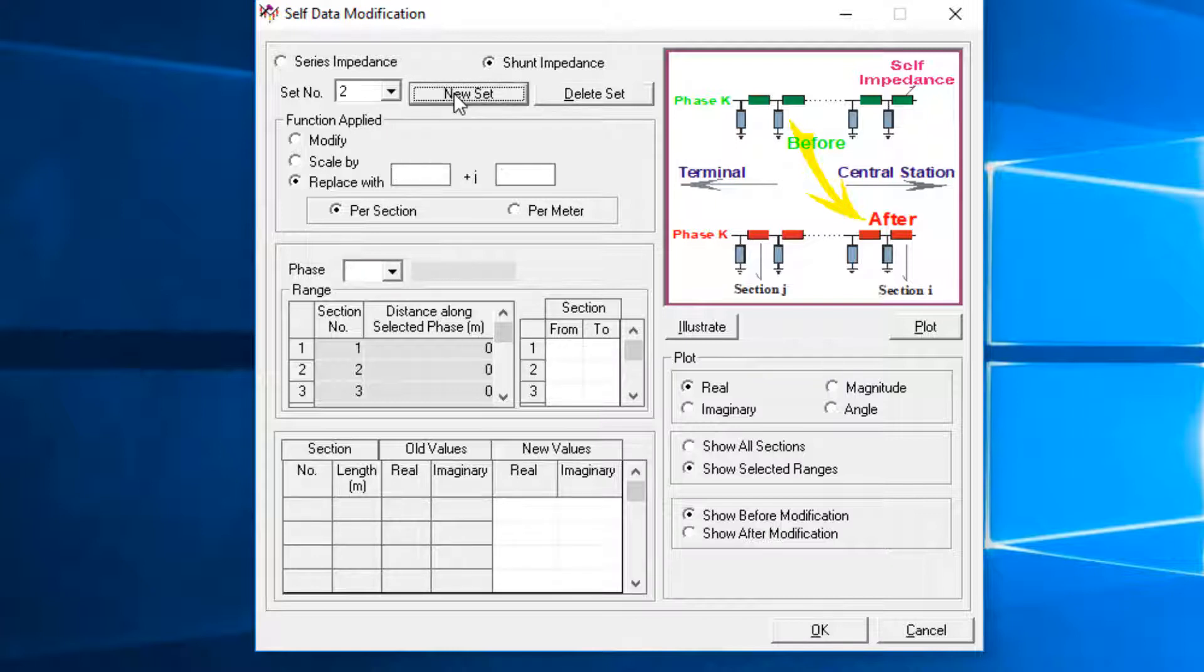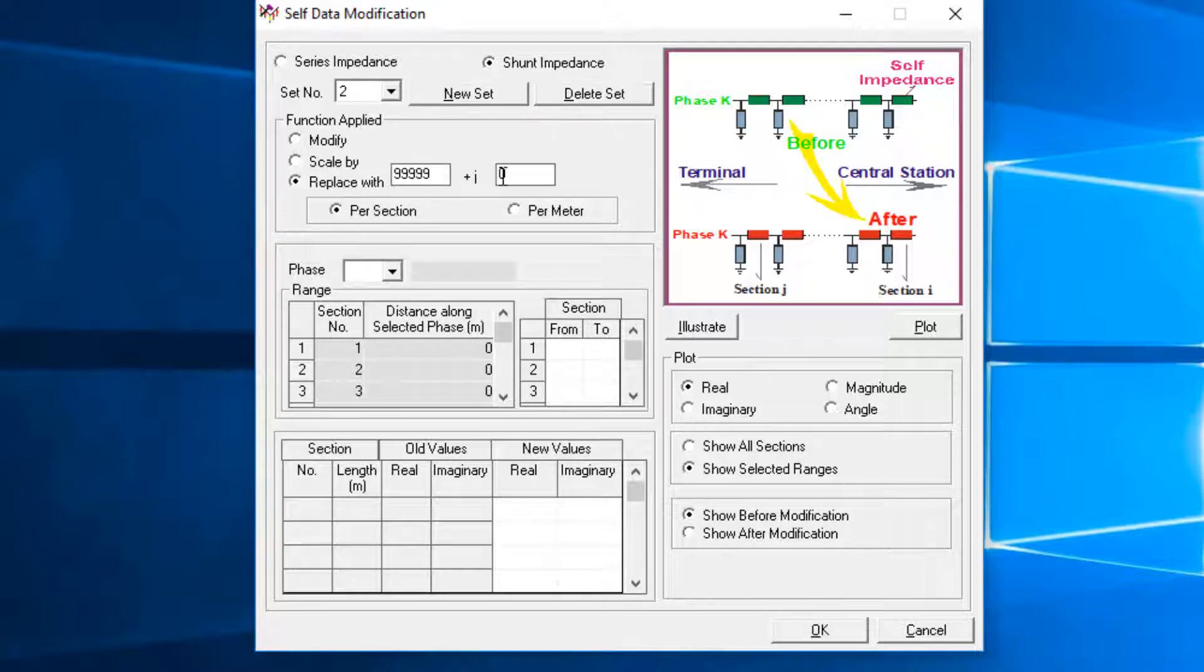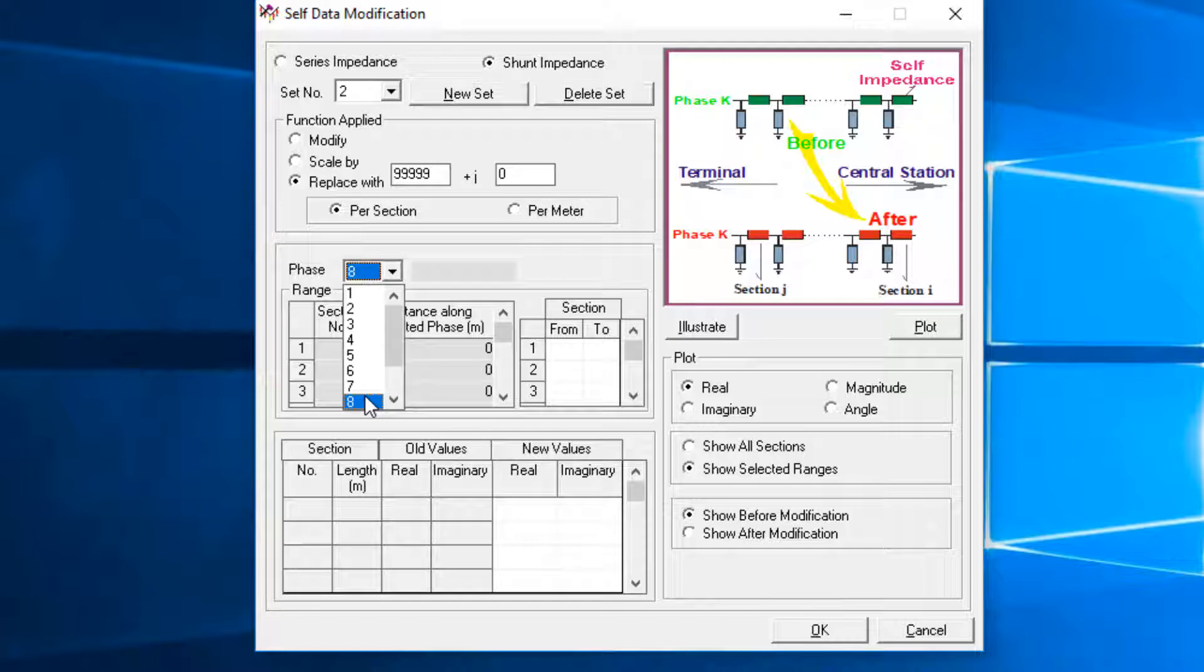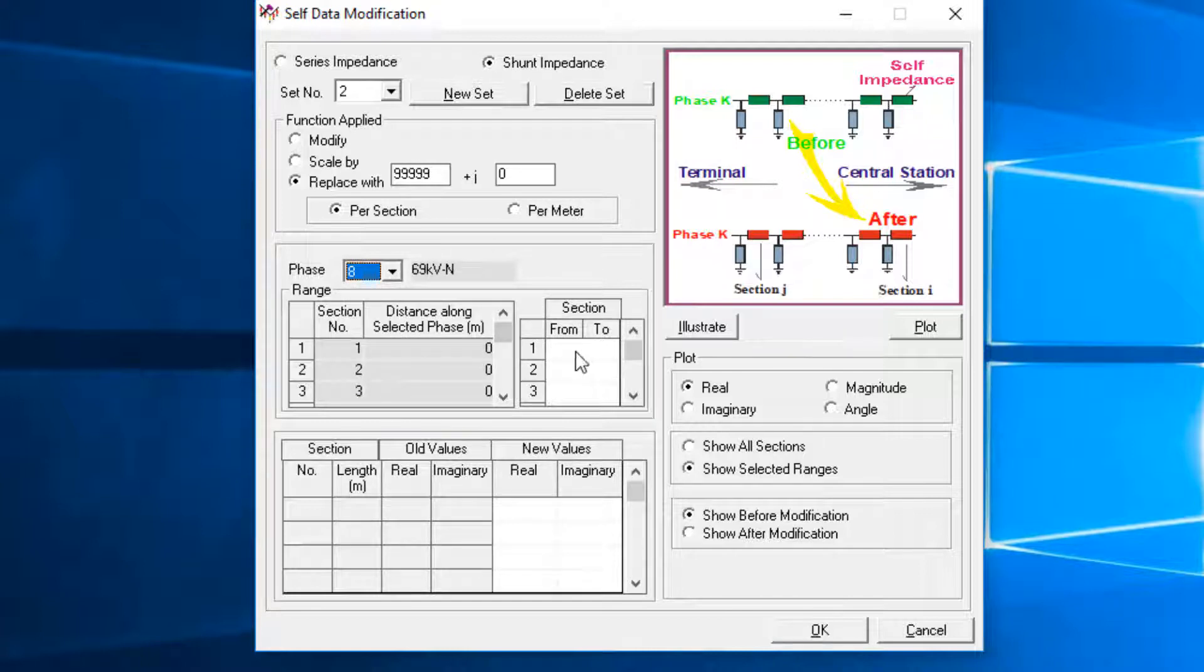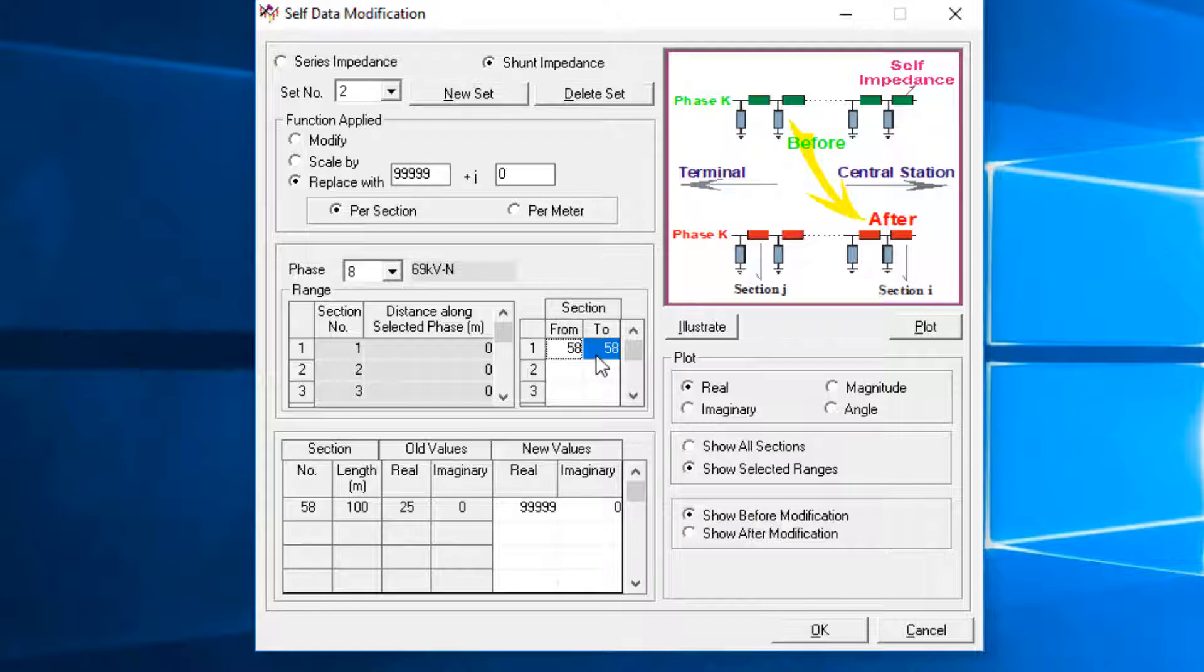Click on the New Set button. Choose Replace With option and enter a large number as the new impedance value. Choose Phase 8, which is 69 kV neutral, and enter section from 58 to 58. This will remove the 69 kV line tower impedance, since the two neutrals are tied at the substation grid.